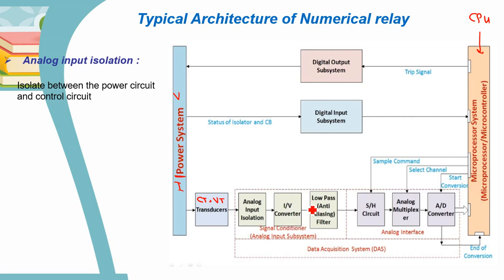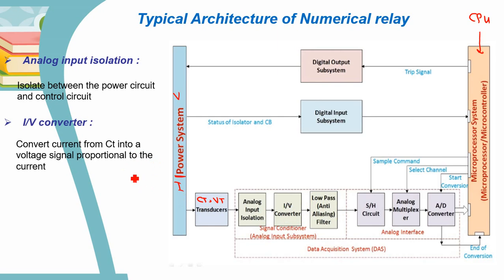Then we have the I-to-V converter — current to voltage converter. The numerical relay only deals with voltage signals, so the I-to-V converter is used to convert the current from the current transformer into a voltage signal proportional to the current. Any signal except a voltage signal must be converted into a proportional voltage signal.